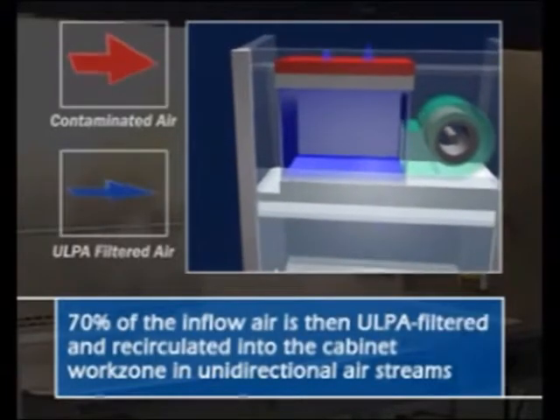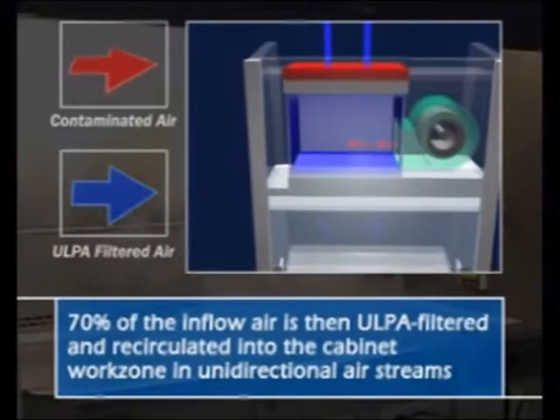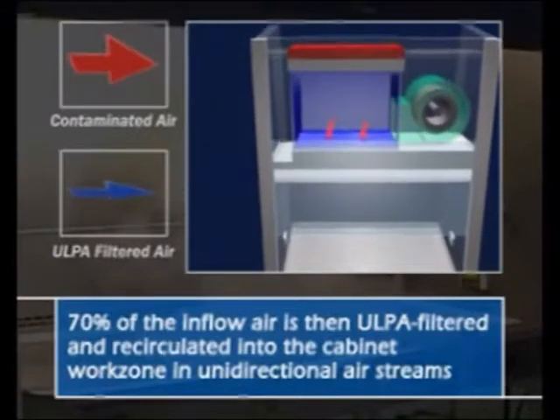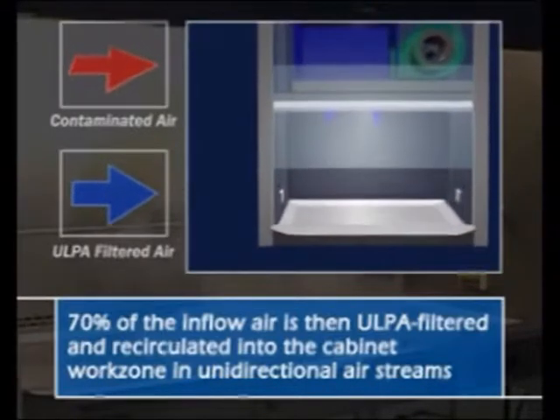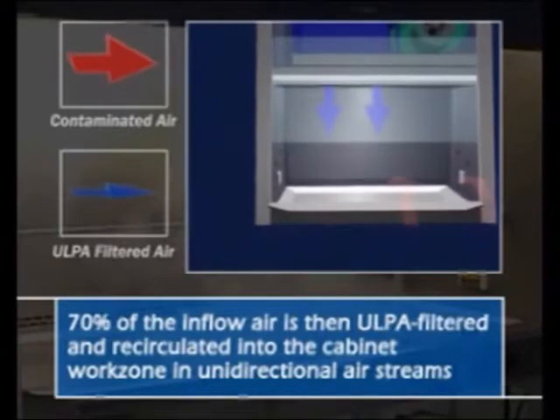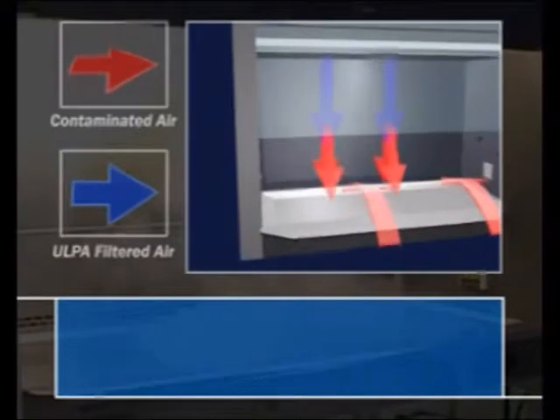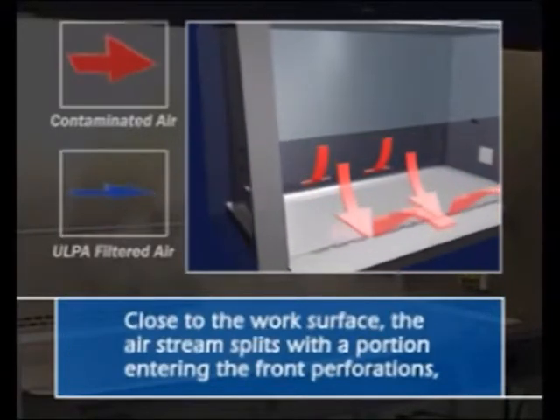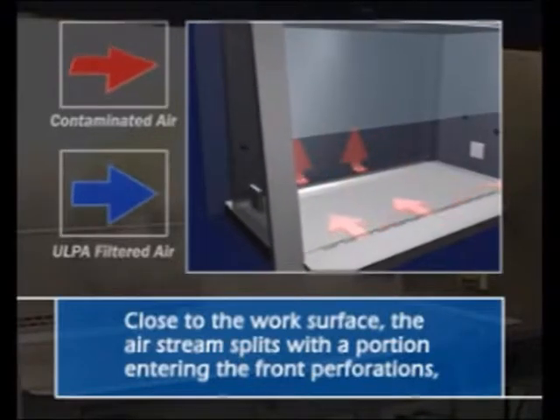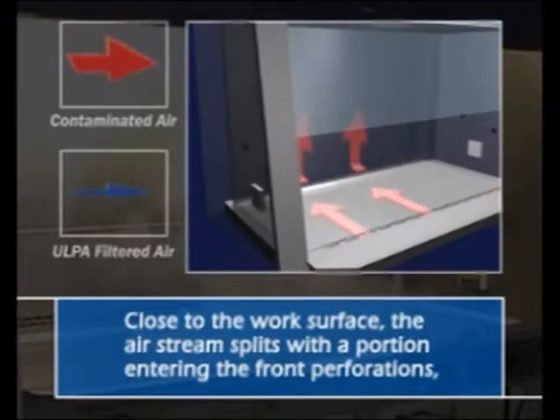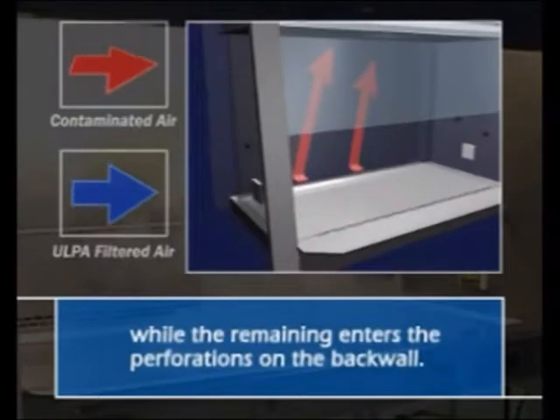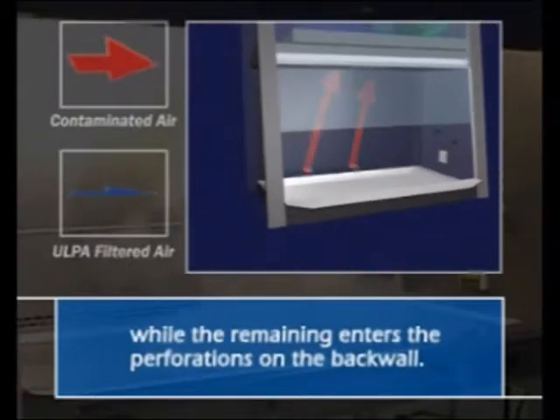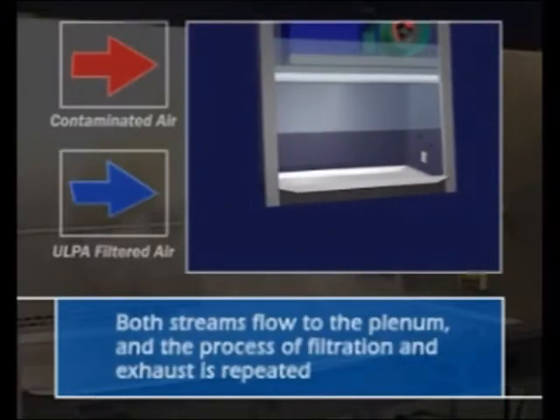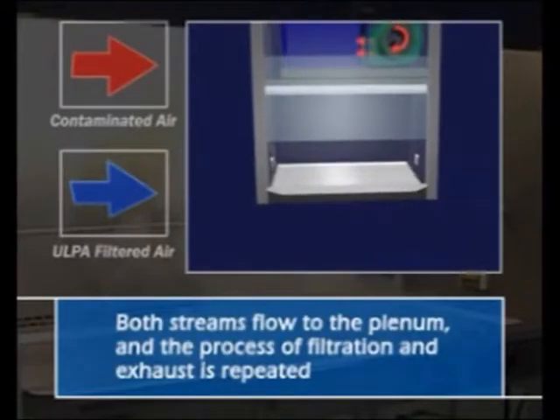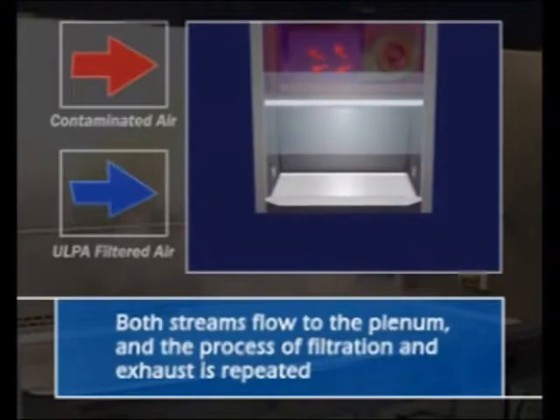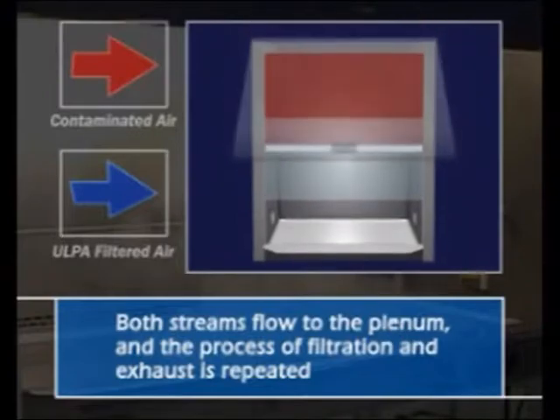The remaining 70% of the air is ULPA filtered and recirculated back into the cabinet work zone as unidirectional or laminar downflow air, providing a sterile and non-turbulent work zone environment. Close to the work surface, the downflow air splits, a portion entering the front air grill, while the remainder enters through back wall perforations. All downflow air is then recirculated to the blower plenum, along with inflow air.